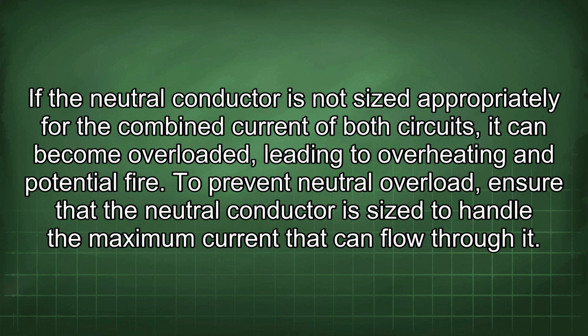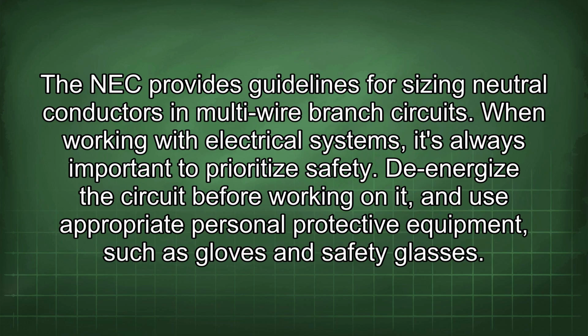To prevent neutral overload, ensure that the neutral conductor is sized to handle the maximum current that can flow through it. The NEC provides guidelines for sizing neutral conductors in multi-wire branch circuits. When working with electrical systems, it's always important to prioritize safety. De-energize the circuit before working on it, and use appropriate personal protective equipment such as gloves and safety glasses.